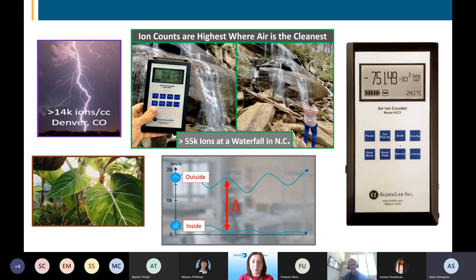So typically with bipolar ionization, you have a finite amount of time to get the ions from where you make them to the space. An artificially produced ion will typically last somewhere around 60 seconds, but you typically want to try to get it to the space within 20 to 30 seconds so that you get as many as you can to the space and you give what you get to the space enough time to have efficacy and interact with the contaminants that may be there that you're trying to remediate. Understand as well, you are constantly bringing new ions in to replace those that have been dissipated through an interaction of some type. So you've got a constant ion concentration or flux reaching the indoor environment.